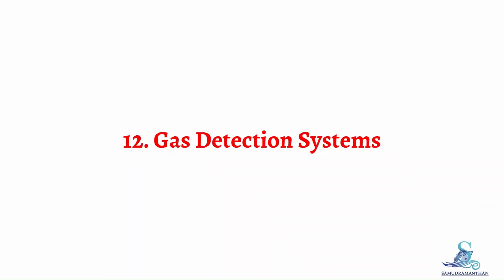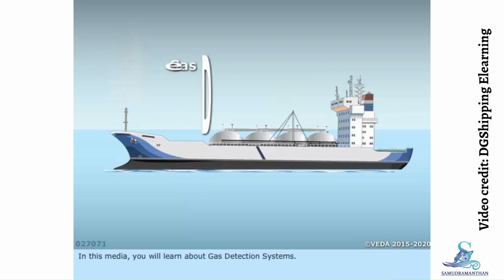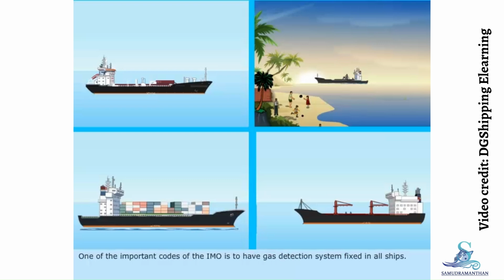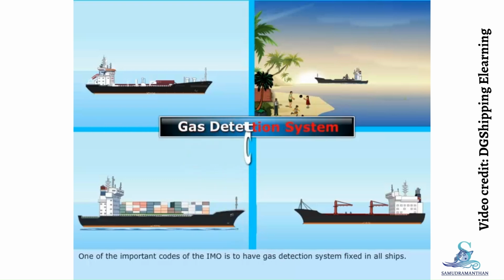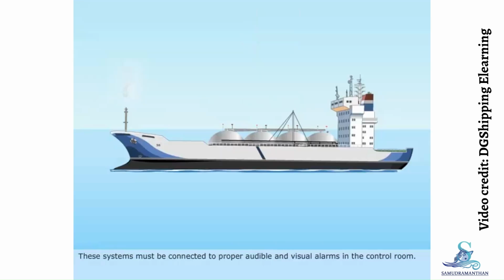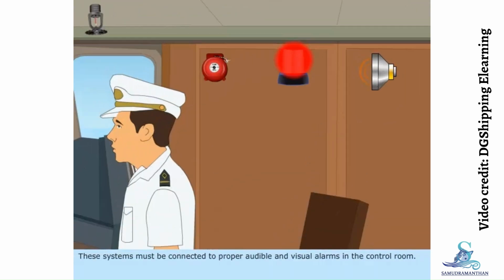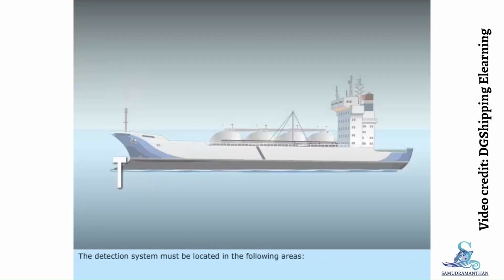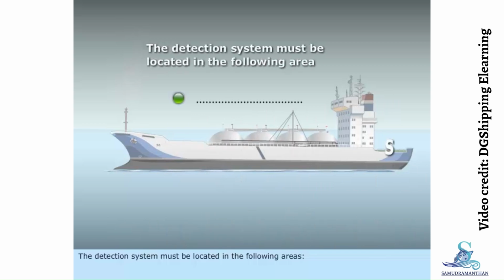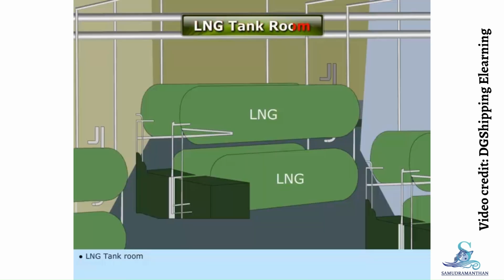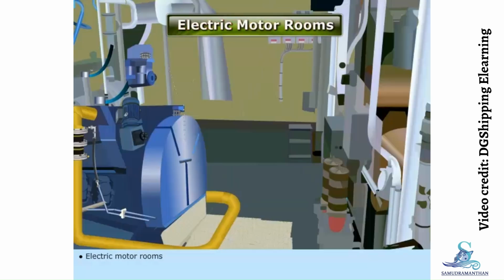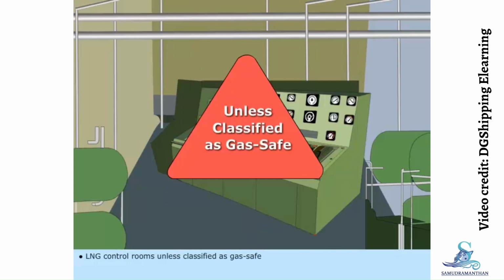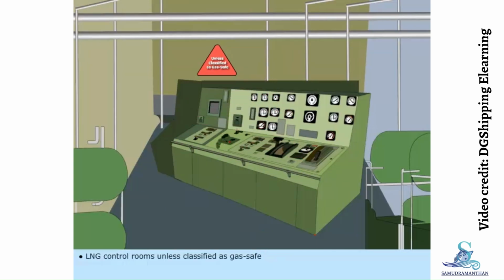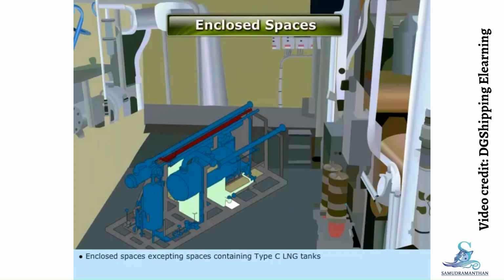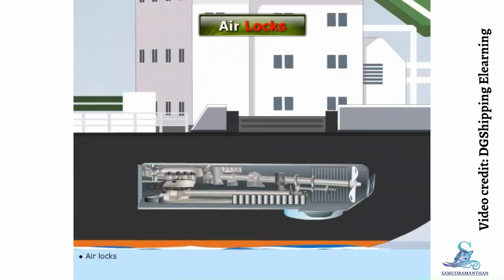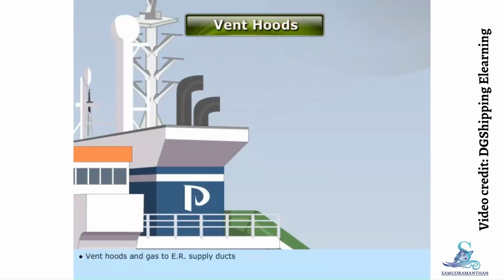Topic 12: Gas Detection Systems. In this media, you will learn about gas detection systems. One of the important codes of the IMO is to have gas detection system fixed in all ships. These systems must be connected to proper audible and visual alarms in the control room. The detection system must be located in the following areas: LNG tank room, electric motor rooms, LNG control rooms, unless classified as gas safe, enclosed spaces excepting spaces containing Type C LNG tanks, airlocks, vent hoods, and gas to ER supply ducts.